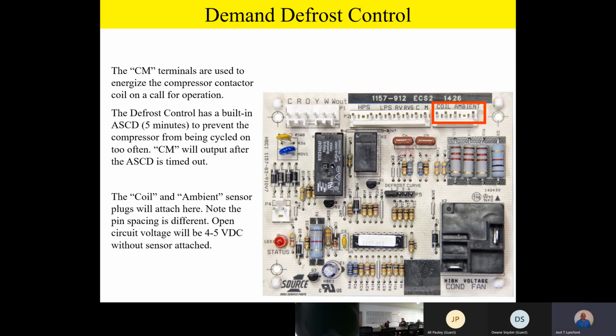Right next to that, there's our ambient and coil sensor inputs. Please notice, team, that the spacing on those sensors is different. And again, it's the same routine. We want to make sure that the ambient sensor doesn't get plugged onto the coil, and we don't want the coil sensor plugged onto the ambient. So if you look closely, you'll notice that the pin spacing is different on the coil and ambient sensors. Now, it should be noted those sensors have the same calibration point, which we'll talk about later. But the demand defrost control has to have both sensors working properly in order to defrost properly. So the coil and ambient sensors are going to be plugged in on the board right there.